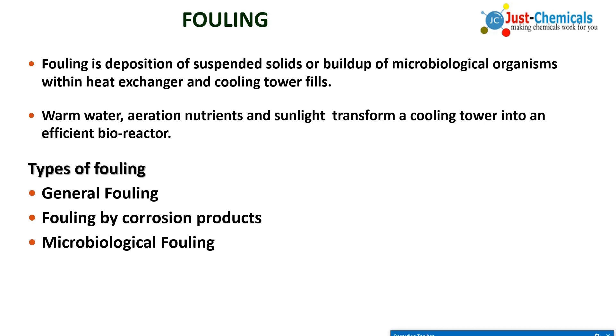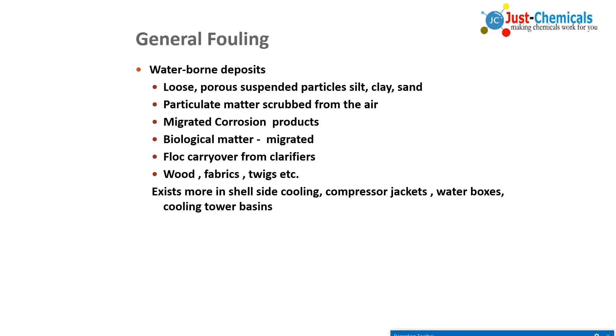For general fouling, loose porous suspended particles, silt, clay, sand, etc. can come in. Then wood, fabric, twigs can also come. Foreign particles in the water, parts of your CW and CT fills, can also come and go into the water boxes. Particulate matter scrubbed from the air, like ash, coal dust, or corrosion product, can migrate. So like cooling tower fills, see how they're plugged with general fouling and microbiological fouling.